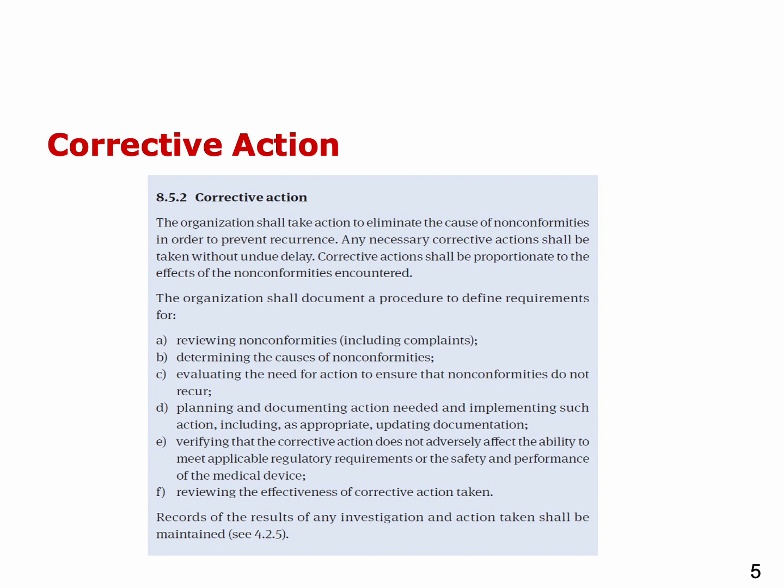And then point E, verifying that the corrective action does not adversely affect the ability to meet applicable regulatory requirements for the safety and performance of the medical devices. And the last point is to review the effectiveness of corrective action taken.